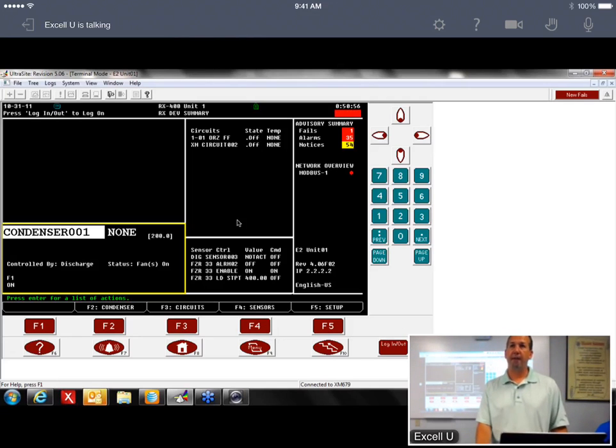Is that a different rate than the CCBs used to pulse at? I don't really know what rate the CCBs pulsed at. You can change what that time period is. There's a setting in the E2 for it, but I wouldn't suggest changing it. The 6 seconds is a pretty good time spot. Digital compressors work the same way. I think those operate on a 20-second window. But with the pulse valve, we need a lot tighter window, so it's always changing percentage, and we change it every 6 seconds.